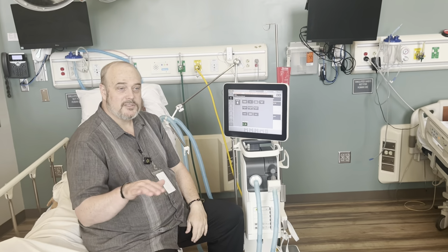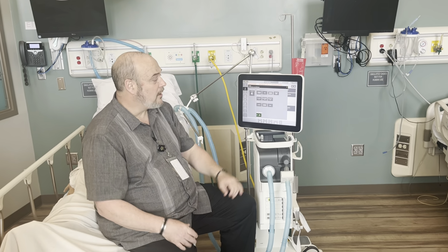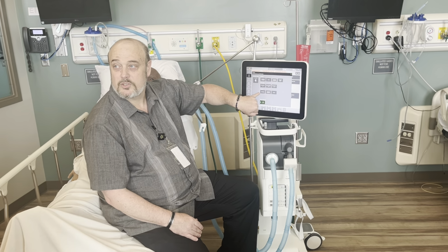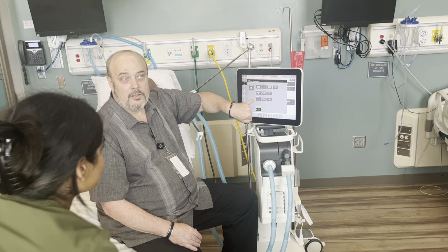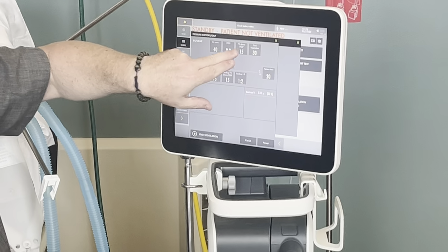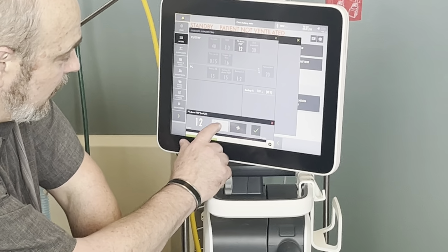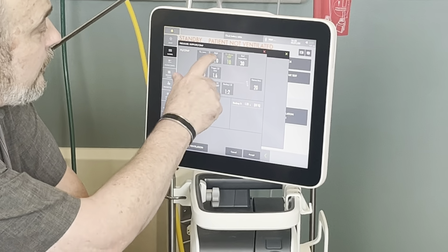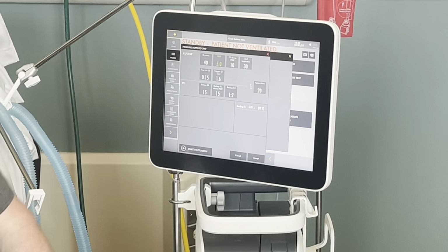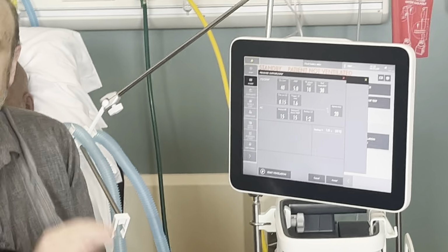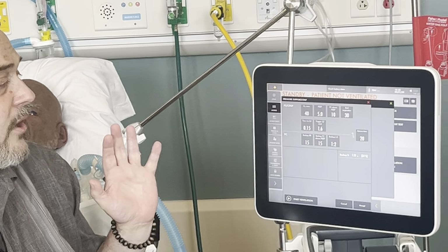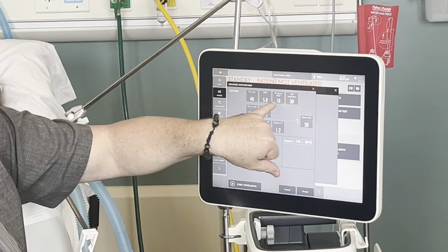So remember we talked about CPAP, then we talked about BiPAP, and then on here we call it PS CPAP, which is pressure support CPAP. So just be mindful. If I press this, it comes over here, and I'm gonna turn that down a little bit. I like whole numbers, a little easier. And the things I'm showing you is that all this stuff you already know, and little changes, they just call them something else.